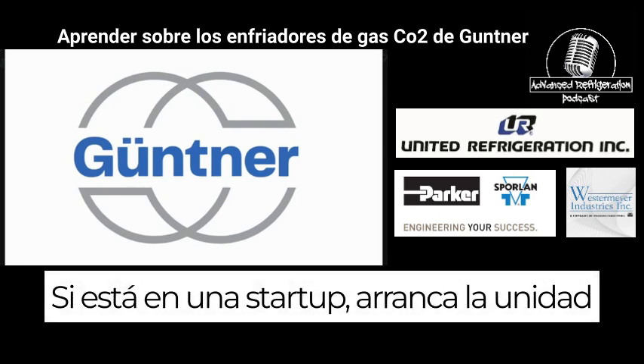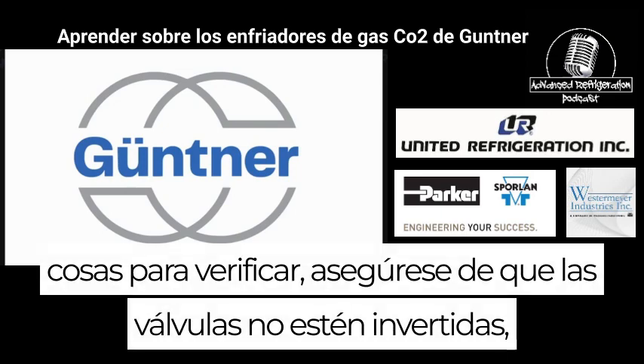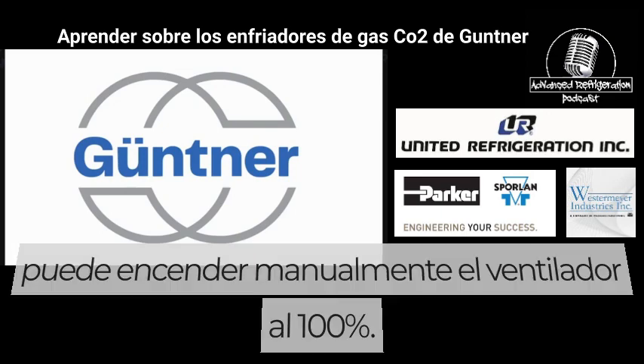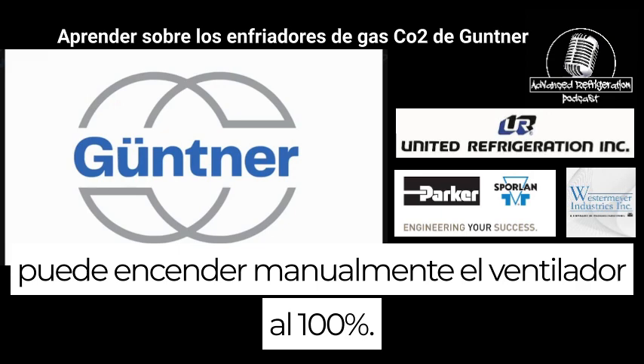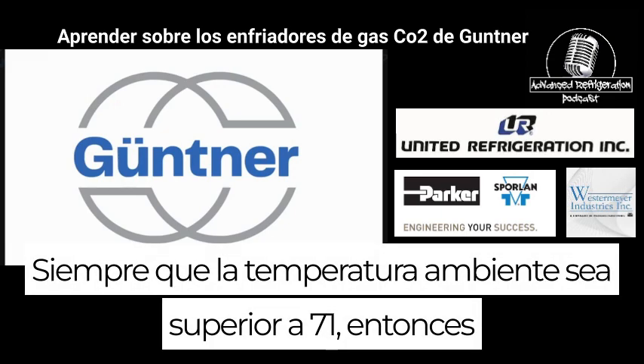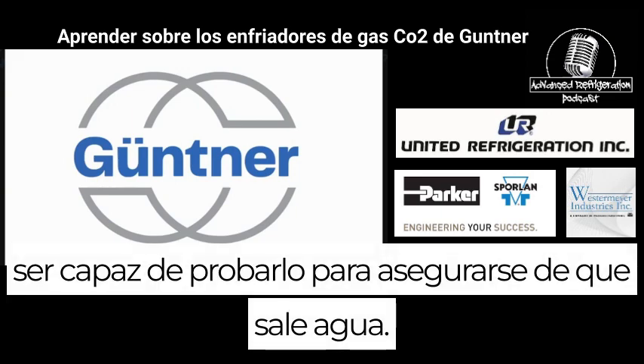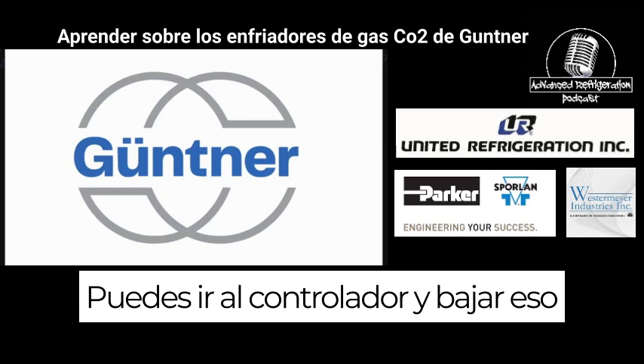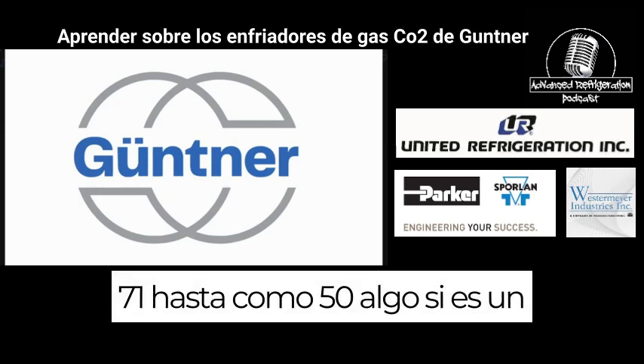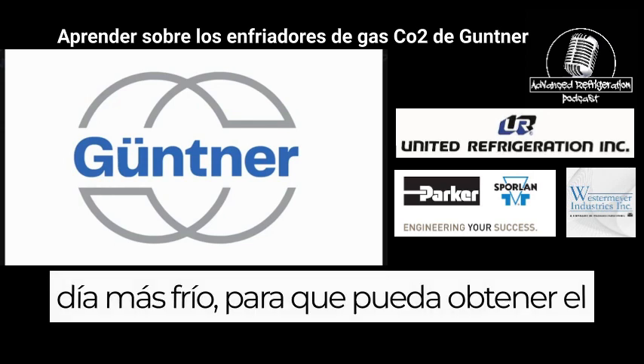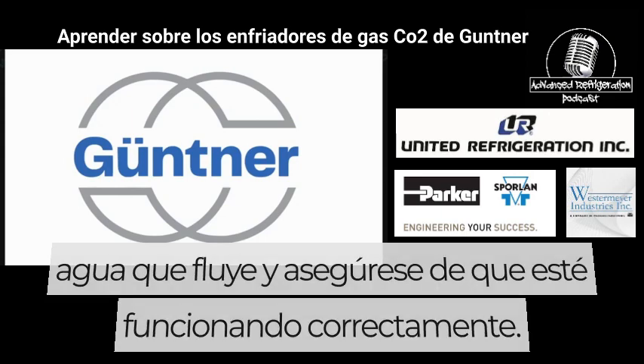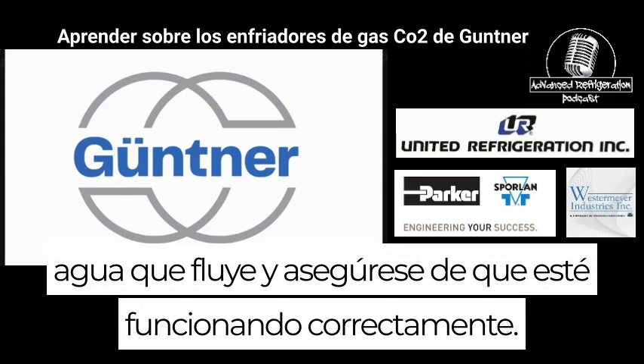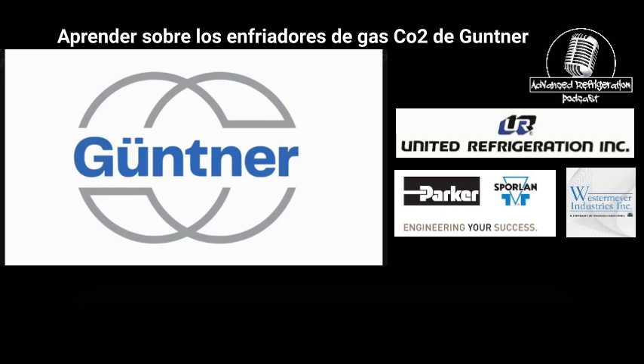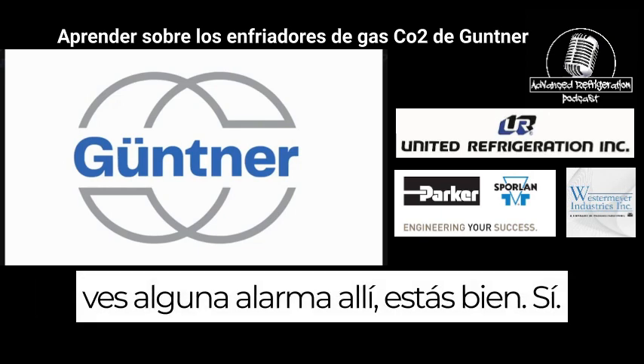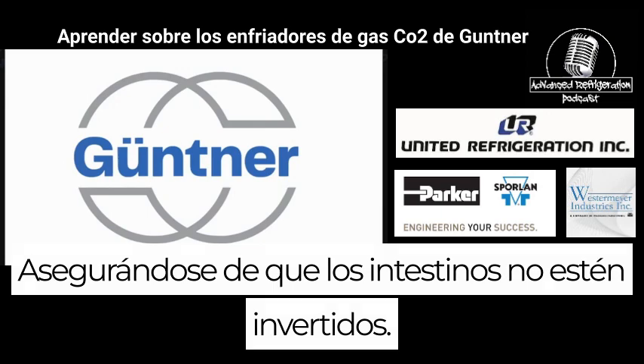If you're at a startup, starting the unit up, things to check for: make sure valves aren't reversed. You can manually turn the fan on to 100% as long as the ambient temperature is over 71, then you'll be able to test it to make sure water comes on. You can go into the controller and lower that 71 down to like 50-something if it's a colder day out, so that you can get the water flowing and make sure it's working properly. But generally speaking, as long as you don't see any alarms on there, you're okay. Making sure the valves aren't reversed.